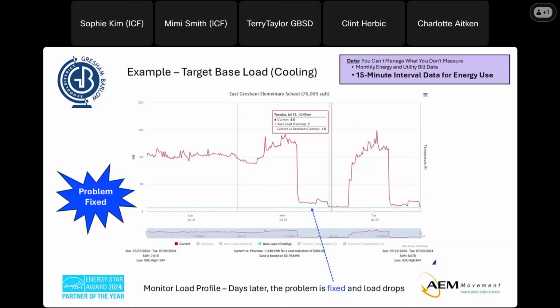And I do have the data for another building. It was a Wednesday night. Our night custodian heard HVAC running, knew it wasn't supposed to be running, and turned it in the next day. That head custodian generated a work order. We dispatched maintenance. They weren't able to get there till Friday. They found out the problem, ordered a part, and replaced it on Monday, and we actually lost $1,000 in those five days with that runtime. But I will tell you that we only lost $1,000.